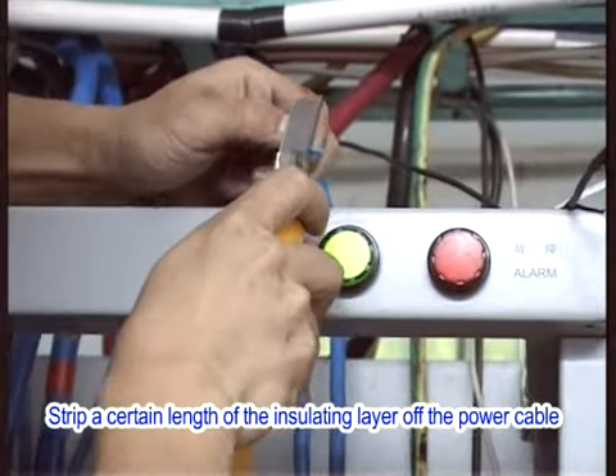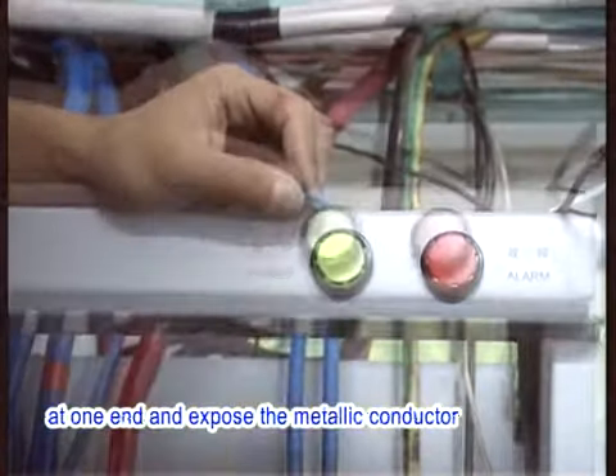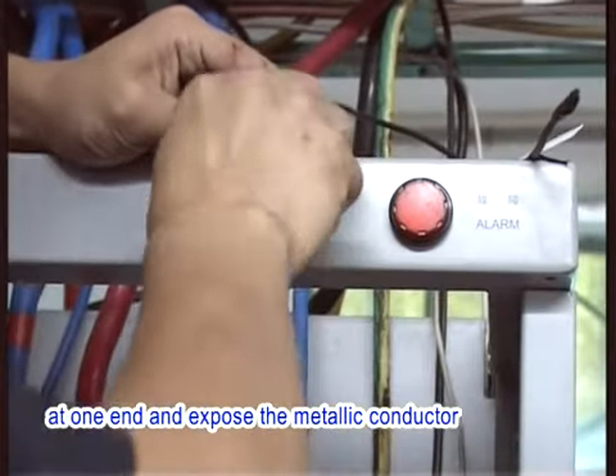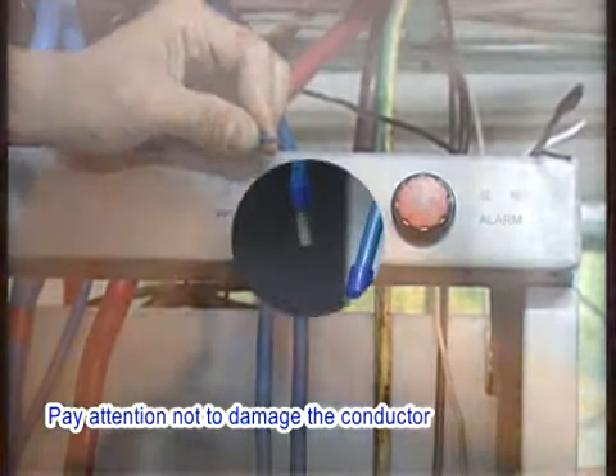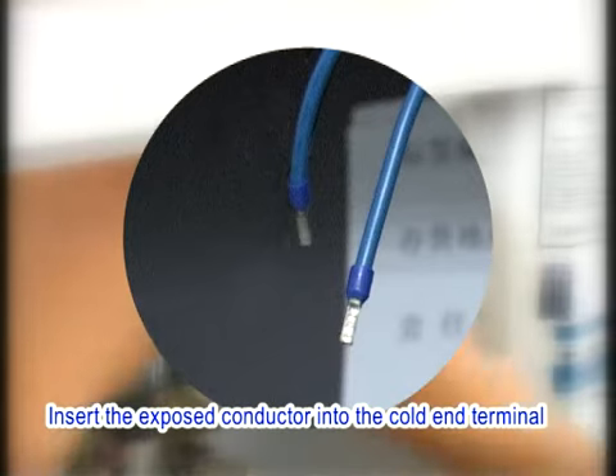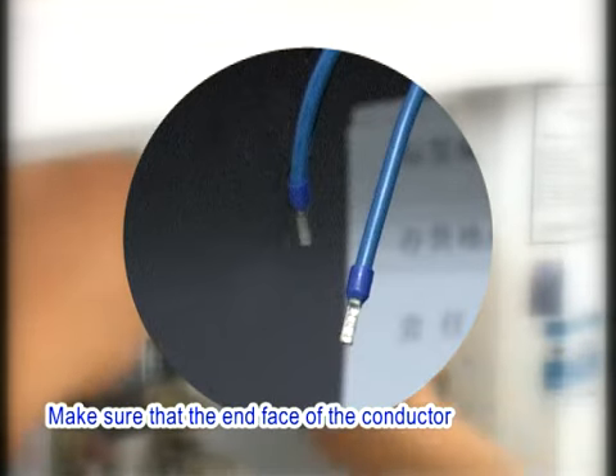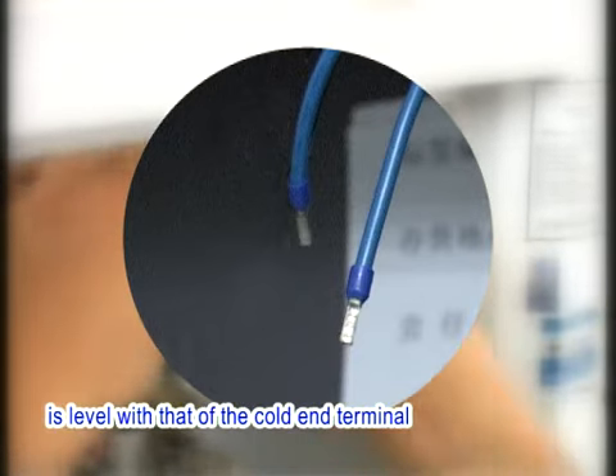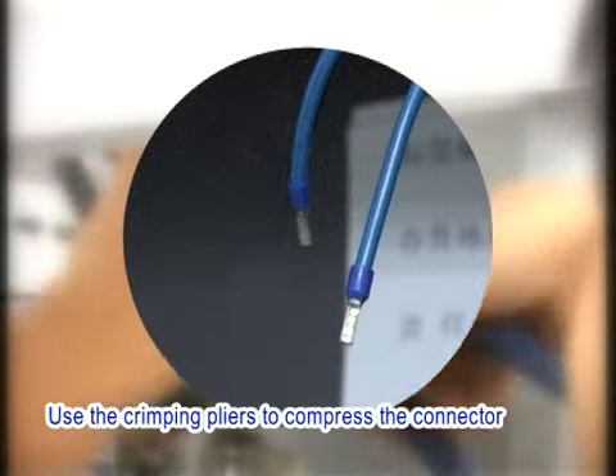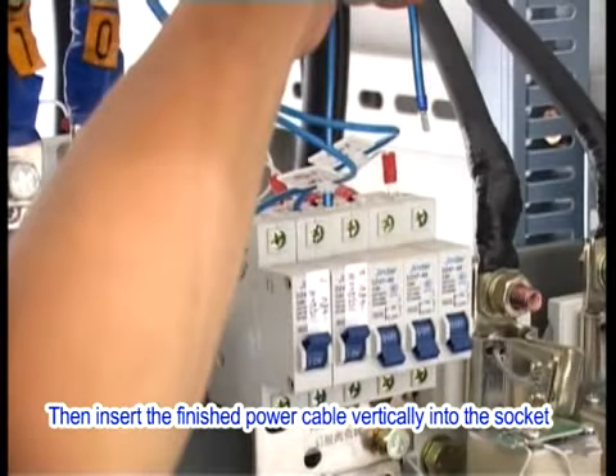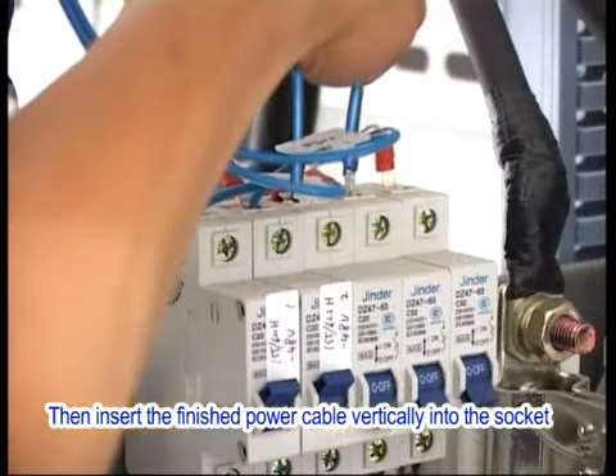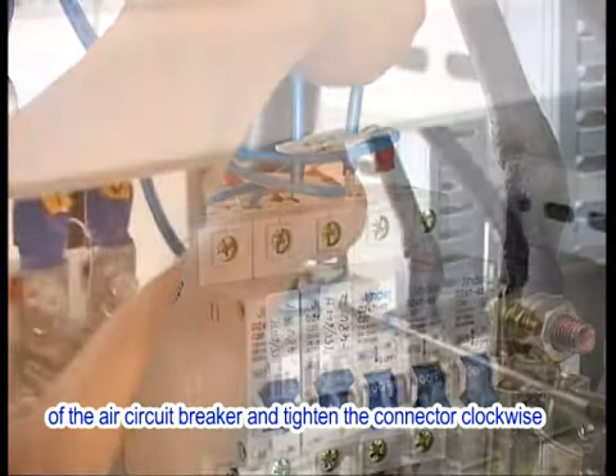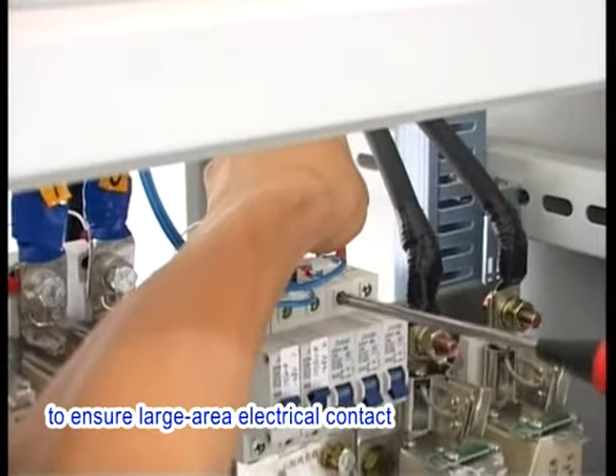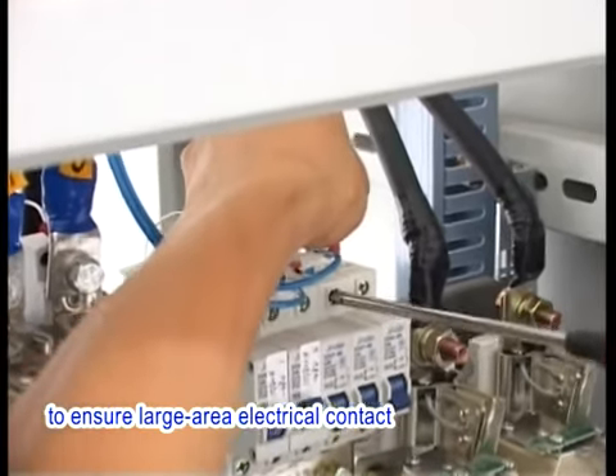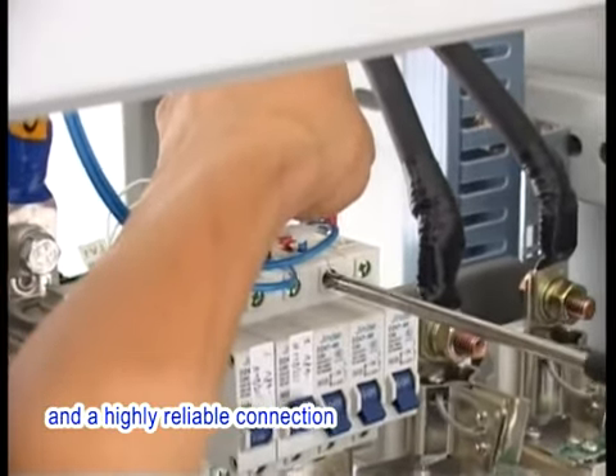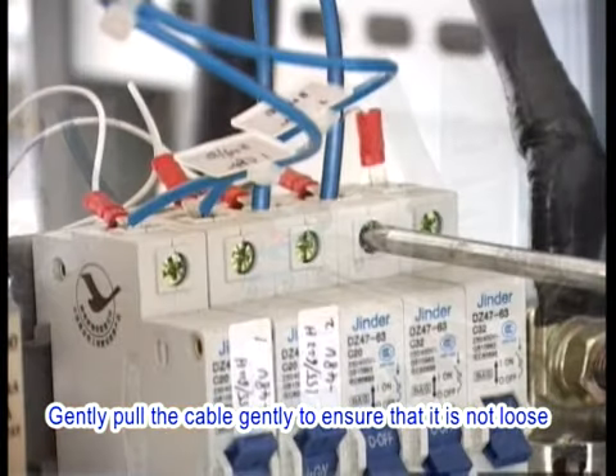How to make the power cable. Strip a certain length of the insulating layer off the power cable at one end and expose the metallic conductor. Pay attention not to damage the conductor. Insert the exposed conductor into the cold end terminal. Make sure that the end face of the conductor is level with that of the cold end terminal. Use the crimping pliers to compress the connector. Then insert the finished power cable vertically into the socket of the air circuit breaker and tighten the connector clockwise. To ensure large area electric contact and a highly reliable connection, gently pull the cable to ensure it is not loose.